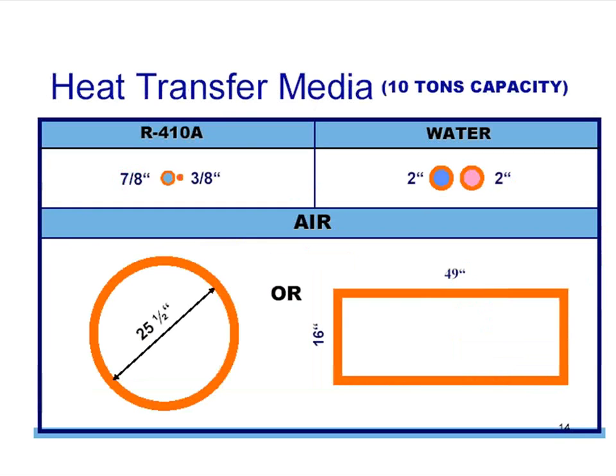Another way to look at it is in reverse, right? So I can say that a refrigerant line set of 7/8 and 3/8 diameters can move the same amount of energy as 2-inch chilled water pipes, which can do the same amount of energy as a 16 by 48-inch duct. I don't know who made this slide for me, but we don't use 49-inch duct, so I'll say 48. So 16 by 48-inch duct, which is a fairly decent size, is the same as a small refrigerant line less than 1 inch. So we can move a lot of energy around.